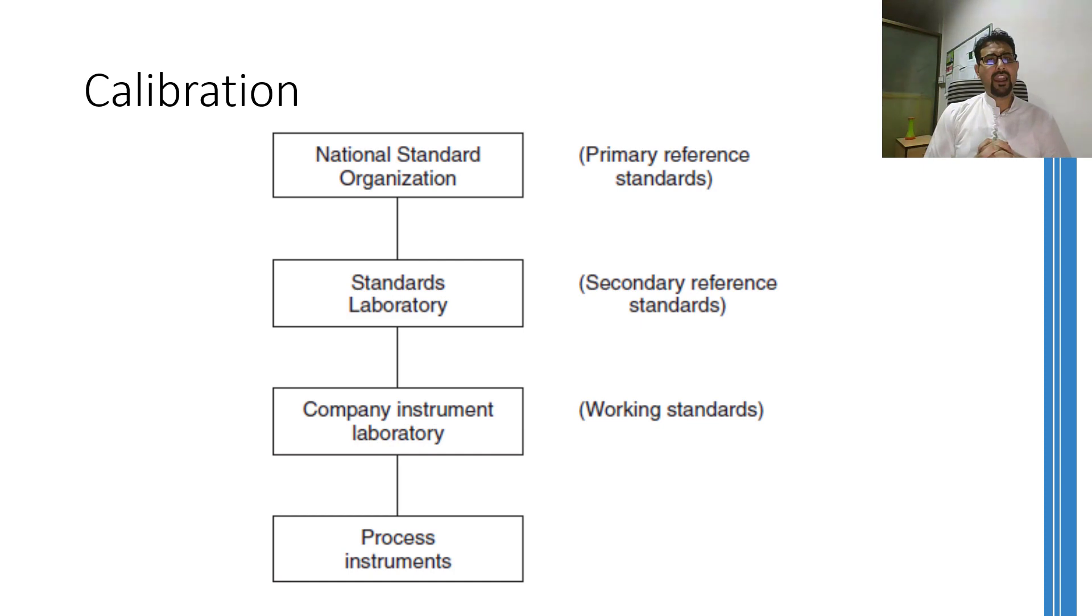This flow graph shows the levels that are used for establishing calibration standards. At the bottom, there are process instruments or the instruments that are used on the factory floor. If they need some kind of adjustment or calibration, they must be compared with the working standards which have been established by the company through their calibration laboratory. This calibration laboratory, which is operating inside any industry, must be in constant contact with the standard laboratories around the country. These standard laboratories are accredited laboratories from the national level organization of any country. So for any country, a national standard organization will define the standards that will be followed by standard laboratories. And if any industry needs any kind of help for calibration or about any standard, the standards laboratory must be contacted.